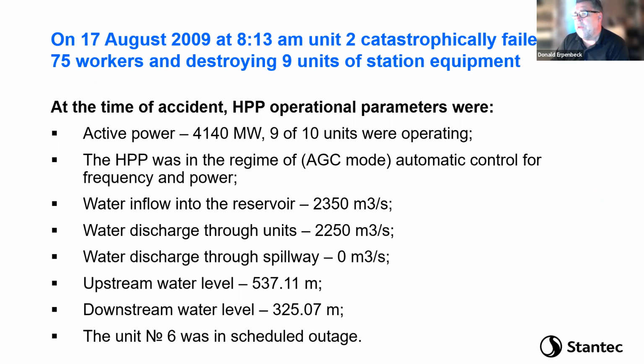The upper reservoir was at elevation 537. The downstream was at 325. So that's 212 meters of head water difference, and the turbines are set lower. So actually it's about 230 meters of head on the pressure containing parts of the turbine that actually failed.